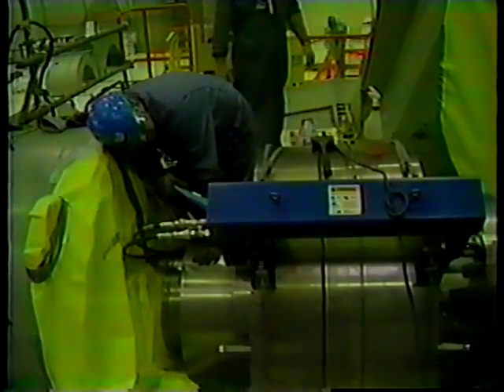After completing a fine mesh screen oil flush, the new turbine was placed on turning gear on day 35. One final critical training session remained. Plant operators were trained and briefed on what to expect during the initial roll and the operating differences the new monoblock rotors presented. After reviewing the startup procedures prepared for this event, turbine roll-off began.